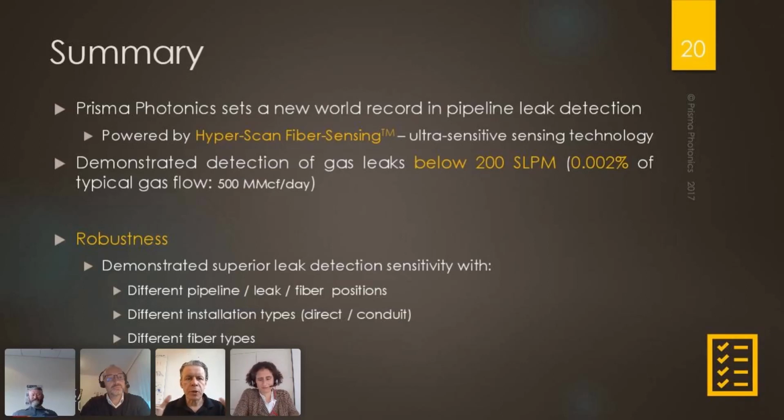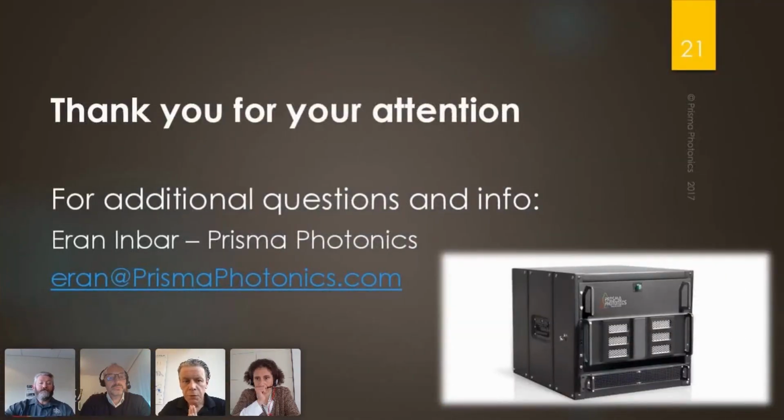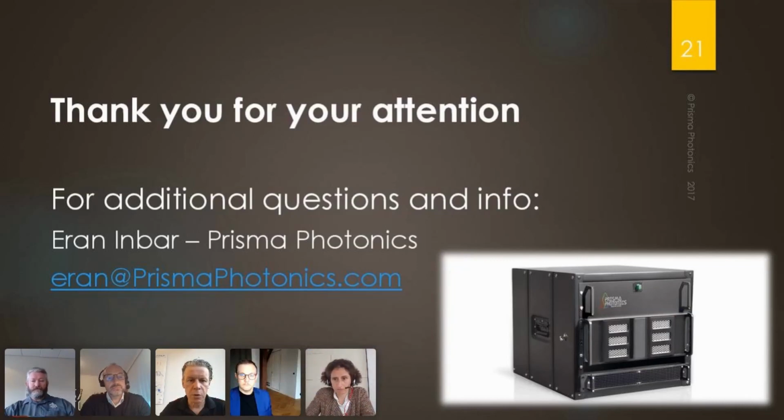So just to summarize what we presented in this talk, it's the world record in fiber sensing pipeline leakage detection based on our proprietary HyperScan fiber sensing technology. We demonstrated gas leaks going below 200 standard liter per minute, which is equivalent to 0.002%. Another important aspect is the robustness of this method. We are not relying on any transient effect, and this method is also not relying on the architecture of the installation of fiber versus pipeline. So we tested it in different pipeline diameters, different pipeline leakages, different fiber positions, different fiber types, and different types of fiber installation. So I would like to thank you for your attention, and we will be glad to try to answer any question there is. Thank you very much.